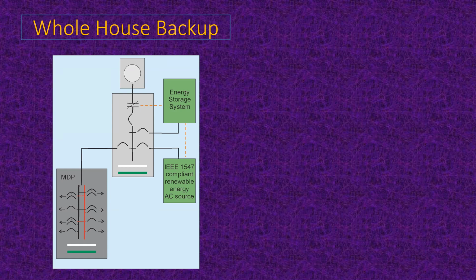In any case, once those contacts break, there's no electricity left unless we have an IEEE 1547 compliant renewable energy source available, which would then generate electricity for the loads in that panel. And at night, if this compliant source happens to be solar, when there's no sun, then the energy storage system has to take over and supply the energy at night. The whole idea here is you need to disconnect from the utility if the utility goes down, because the people trying to fix it don't appreciate it if somebody's solar system is dumping an extra 7,600 volts onto one of the lines in the street while they're trying to fix it. So that's IEEE 1547 for small systems: you've got to disconnect so the utility can work on getting the power back up.